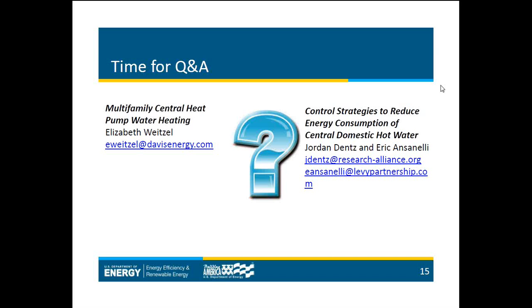And the next question is, what was the typical flow rate for demand control pumps? So we spot measured this a few times at the buildings, just at the beginning of the study. For the flow rate of the recirc pump, I think somewhere between 12 and 22 GPM, depending on the building.